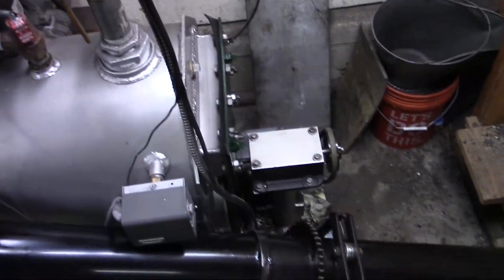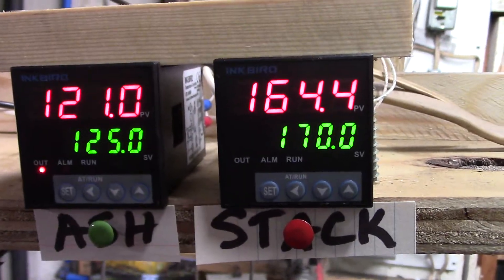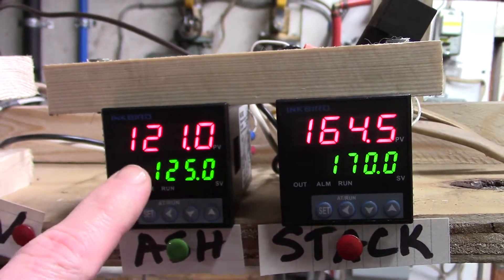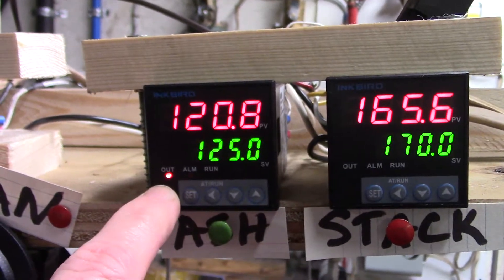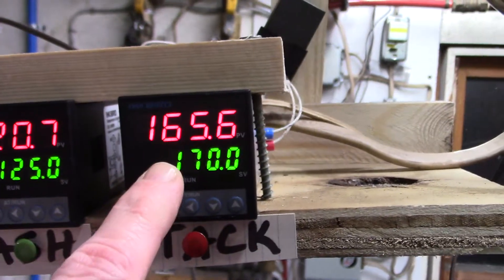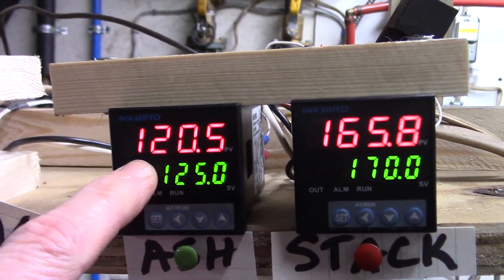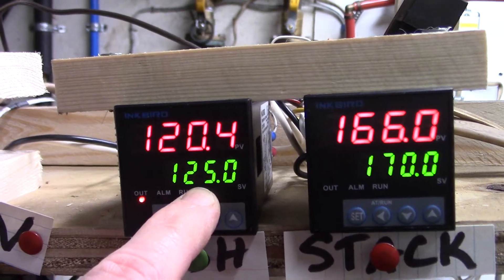As you can see right now the ashing temperature, this just came on, it's actually running right now. The fan is just running right now because it's actually in stack temperature inhibit right now. So the ash temperature has dropped below the set point so the output is activated on this one.